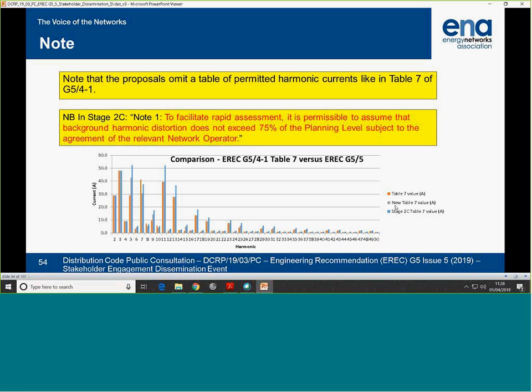And the third column, the values in blue, are if you put it into stage 2C and work out, if I sat at 75% of the planning level, what current would it take to get me up to the planning level? And you can see that the fifth is then higher, the seventh is slightly lower, the 11th is higher, the 13th is higher. So this was a way of trying to meet both requirements: taking the table out so it couldn't be misquoted, but giving it as a way of being done so that it could be used as a way of assessing things quickly. So that might be of interest to DNO people here in particular, or us.